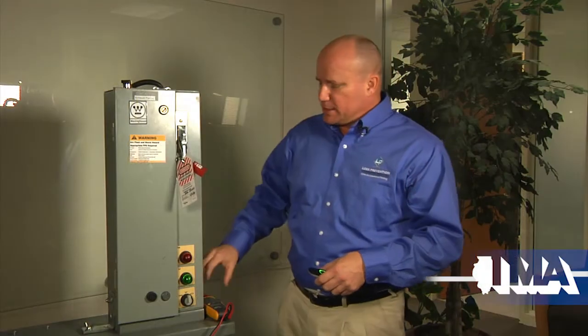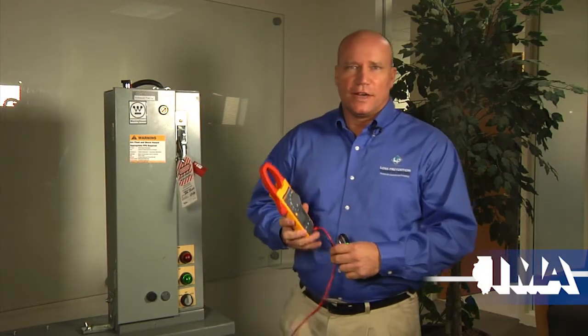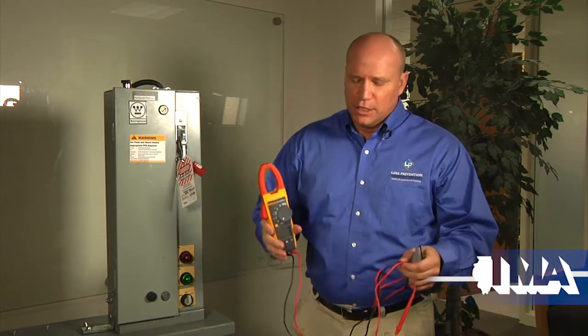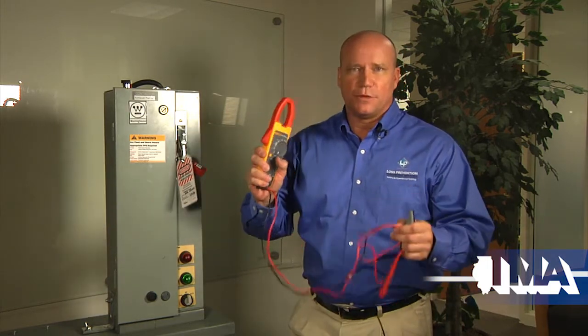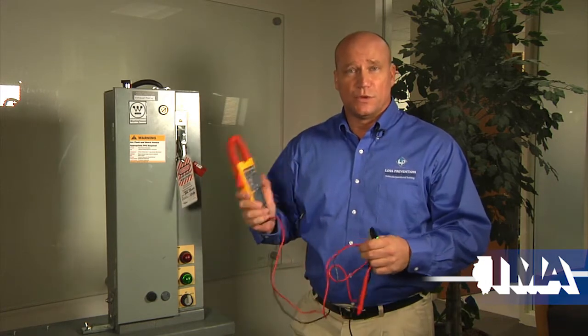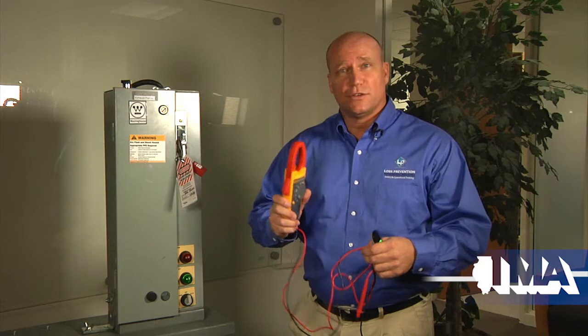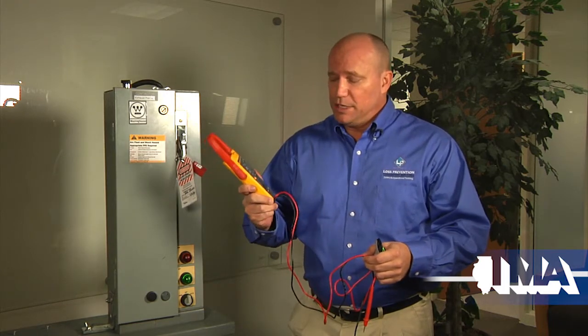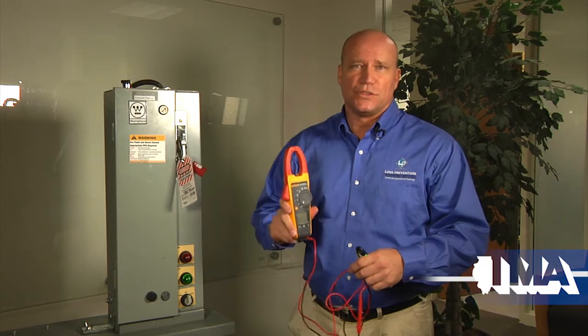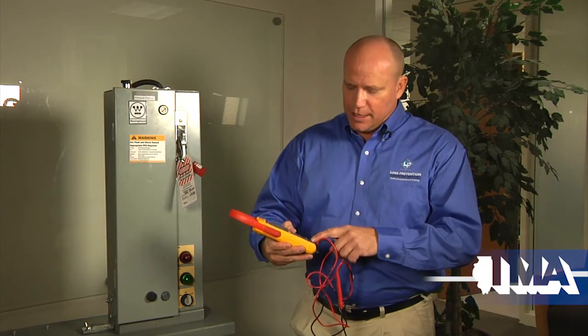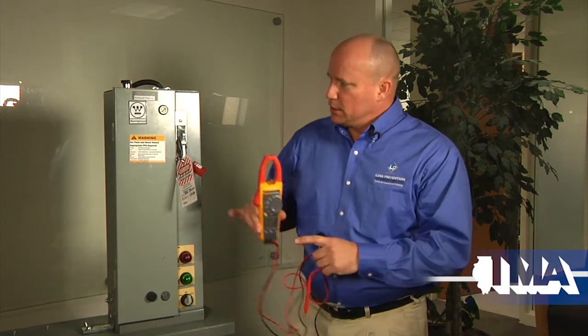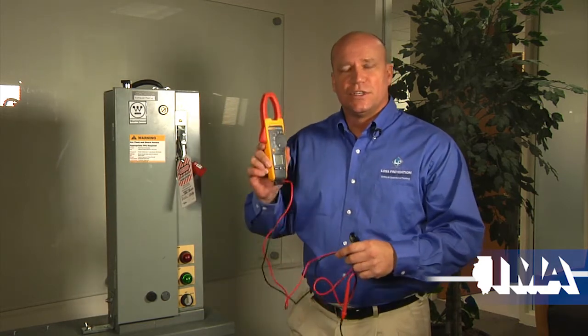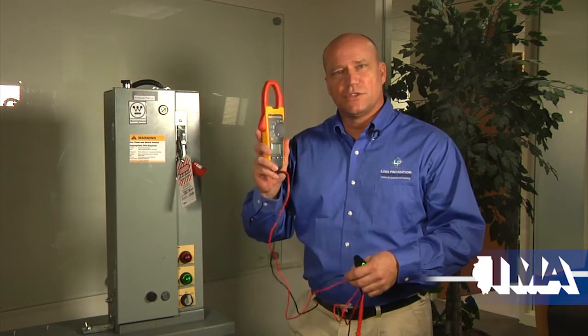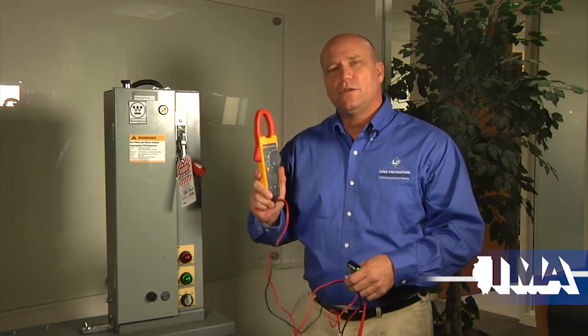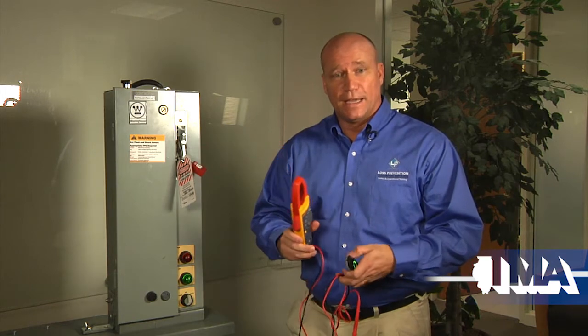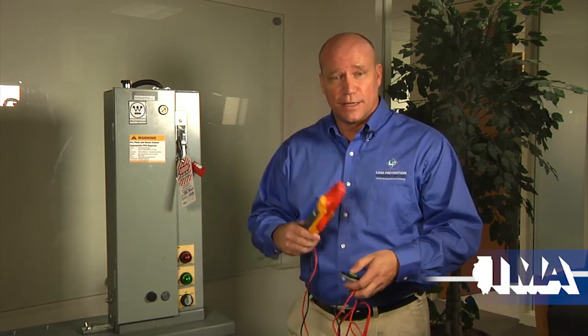First thing, we'll go ahead and get started on this: how to actually do a correct live dead live or verification. The first part in the process is to make sure your meter is adequate and is going to protect you if it were to fail, and then selecting the right meter so it does not fail. So I need to have the right rated meter. And it's not just the voltage rating that you have to be concerned about. This is a 1000 volt category 3 meter. This is a 208 volt controller, and 1000 volts is obviously greater than 208, so voltage-wise it's able to protect me. But what's also equally important is the category of the meter. And we'll talk about that in the subsequent slide here.